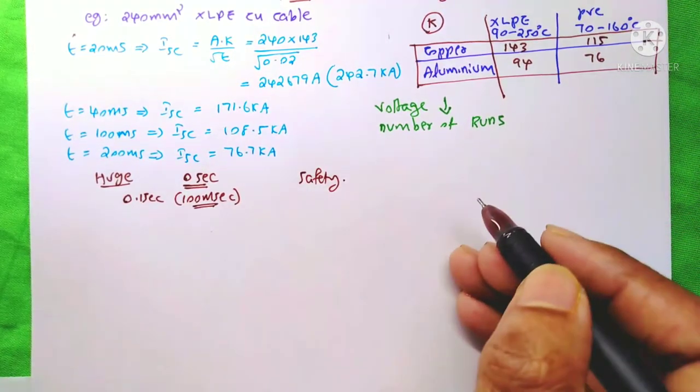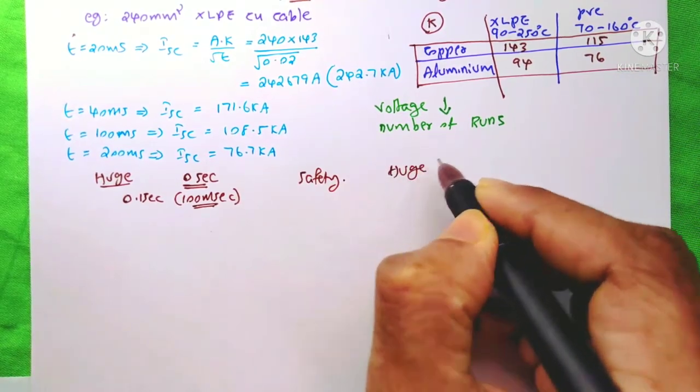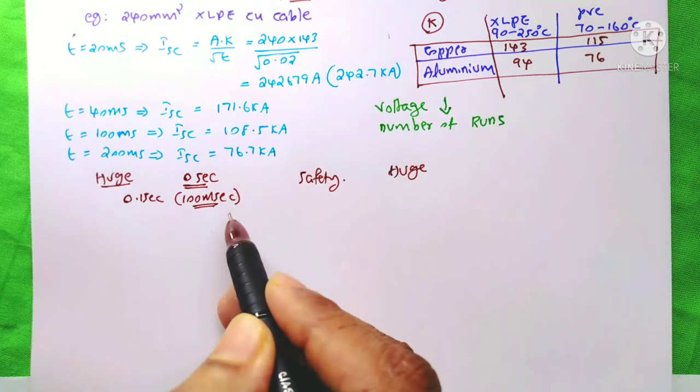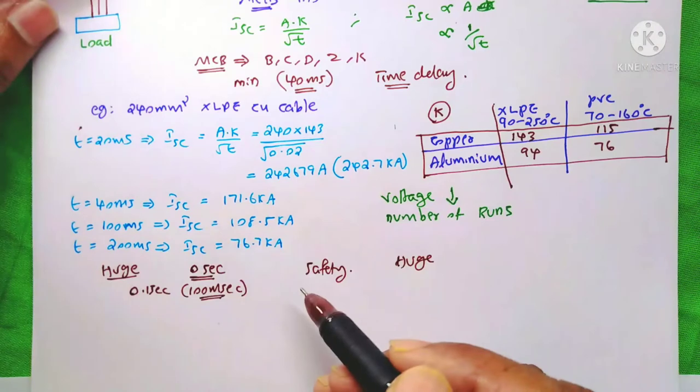if a circuit breaker cannot trip instantaneously, then at that time also our cable can handle the huge short circuit. So if we consider some delay, then our short circuit capacity of the cable decreases.